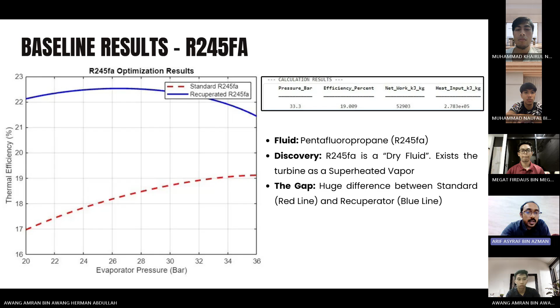The difference between the dashed line and the blue line represents the excess or waste heat that exits the boiler. So why does R245FA have so much waste heat? Because it is a dry fluid, meaning that when it exits the turbine, it exits as a superheated vapor. The state of the organic fluid exiting the turbine is superheated vapor, so there is a higher amount of waste heat that the recuperator can absorb from the turbine exit.